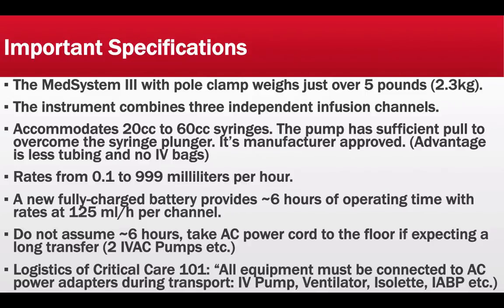As we said, a new fully charged battery, as per manufacturer, provides around 6 hours of operation time with rates of 125 mLs per hour. So it's rarely that you have all 3 channels going at 125 mLs an hour. Some may be going at 200 mLs an hour, 100, and so forth. And you could use a backlight display and utilize it during programming. So I do not assume 6 hours ever. I always take the AC power cord with me whenever I go to the floor. The reason being, you never know how long the transfers will take.